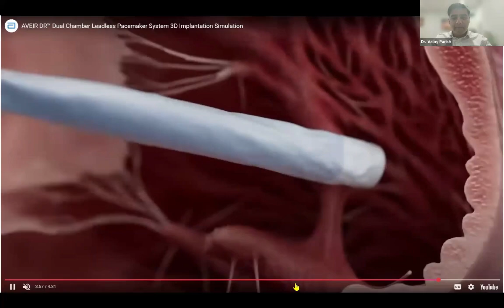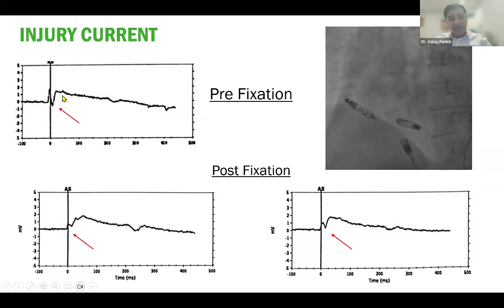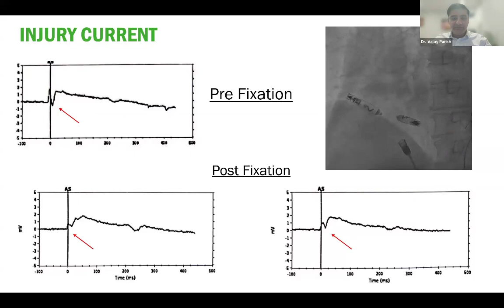Before the device is released, the Aveir devices have an option to look at electrical parameters and decide if this site is acceptable. The Micra device, which is a tine-based device, is placed based upon target location. It does not have any pre-release electrical parameters that need to be checked, while the Aveir device has an option to check electrical parameters and decide if this location is good enough. In this example, in pre-fixation EGMs, you can see a nice local ST elevation or injury current, while after the release, you can maintain that ST elevation, and it gives better electrical parameters over time.